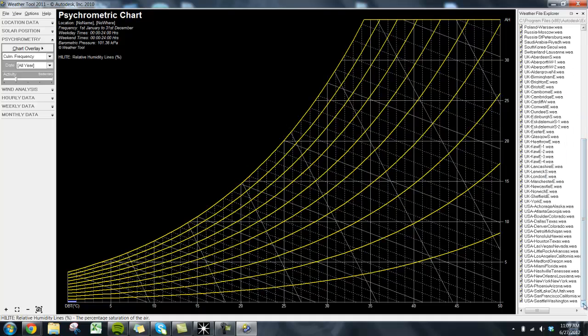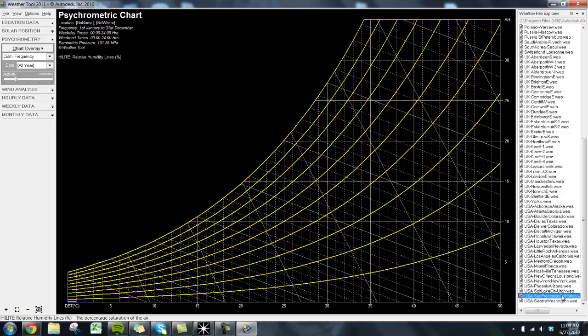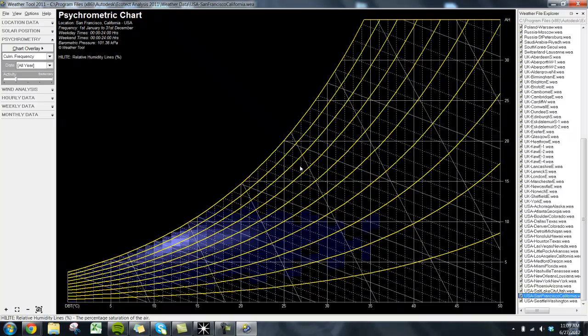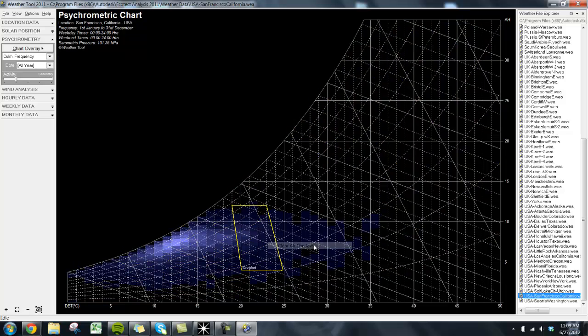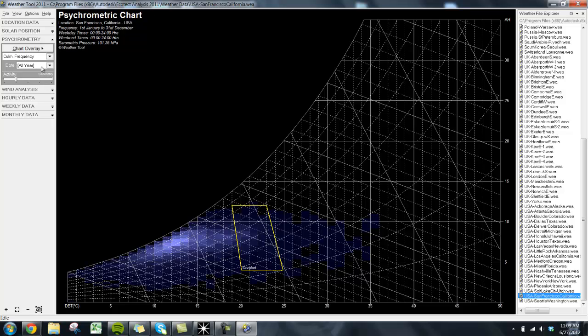Next, we'll load a weather data file and see what it looks like. Here, we'll see what San Francisco's weather looks like on a psychrometric chart. From the data, we can immediately tell a few things. First, the areas that are colored more brightly occur more often throughout the year. This means that the most common weather in the city is cool and moist. This is easily seen if we just look at the hourly data points.